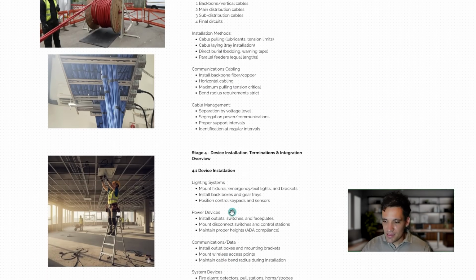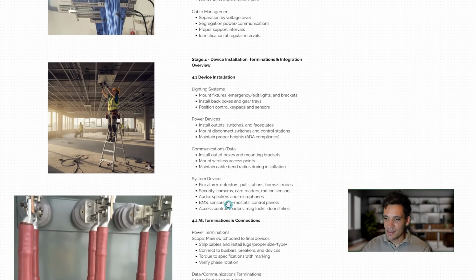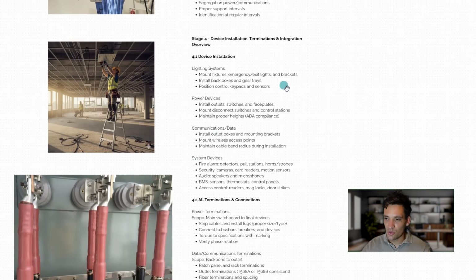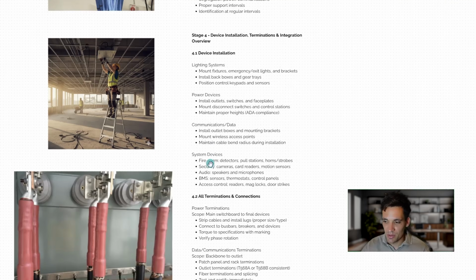Now, once all the main cabling's in and the cable trays are in, the next step is to go through and install all our devices. So for lighting, we're mounting fixtures, the emergency light fittings and the brackets. We might be installing power outlets. We're mounting our disconnector switches, and so on and so forth. And again, this is heavily connected with building fit out, so putting up the walls, coordinating all these tasks with the building construction.